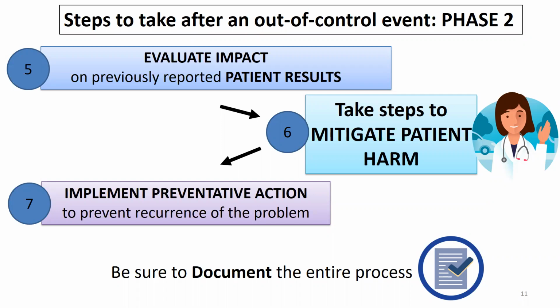So preventative action is not only correcting the problem in the short term, but ensuring that the problem does not reoccur. That could mean replacing parts or scheduling instrument maintenance more frequently, or changing onboard expiration dates so that reagents are changed out more frequently, or even changing the QC rules so they detect the problem earlier.